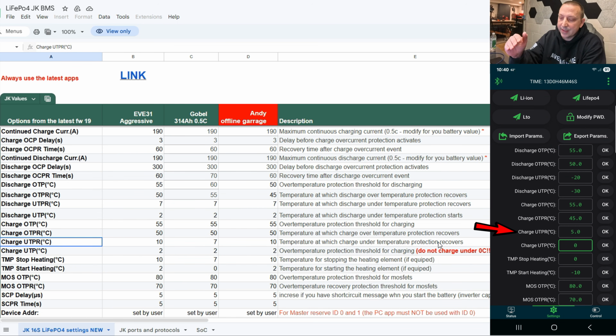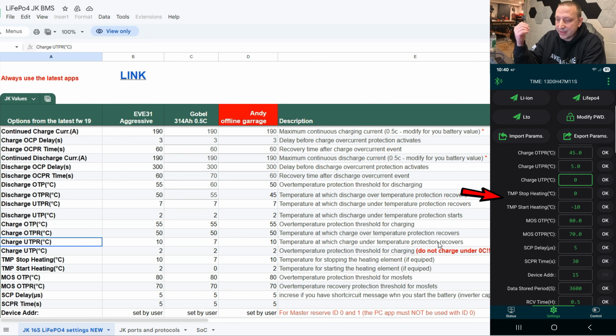This one they've got backwards again, so my brain works a little different. The charge under temperature protection release is set for 5 degrees C, and the actual protection right below that is set for 0 C. I did change that one, don't remember what it was previously. Basically you don't want to charge your batteries when they're freezing. It's got some heating settings, but this doesn't have any heating in there, so I didn't change any of that.